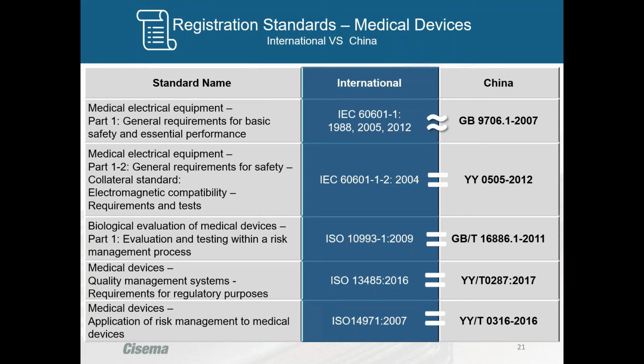On the first row, you can see the electrical safety standard for active medical devices. In comparison with the international standard, they would be similar to about 85%. If you look at the electromagnetic compatibility standard on the next row, this is the test standard for electromagnetic compatibility tests in China. And here you might notice that the Chinese standard is identical to the old version of an international standard. Most countries now use the 2014 version, but that's not the one that China wants to compose their type tests in accordance with.